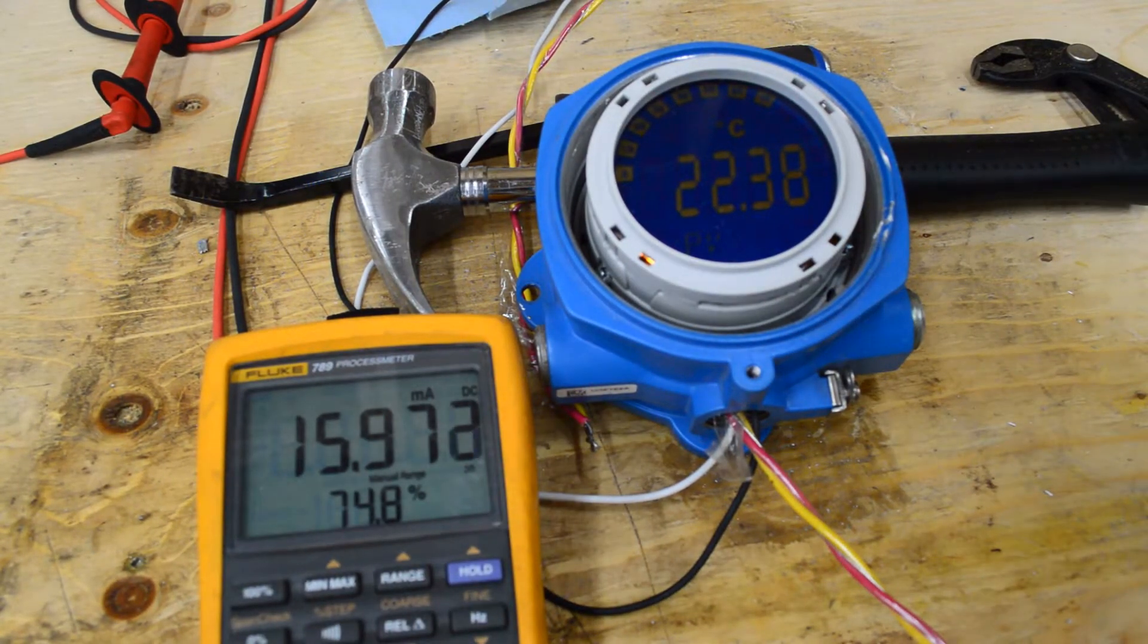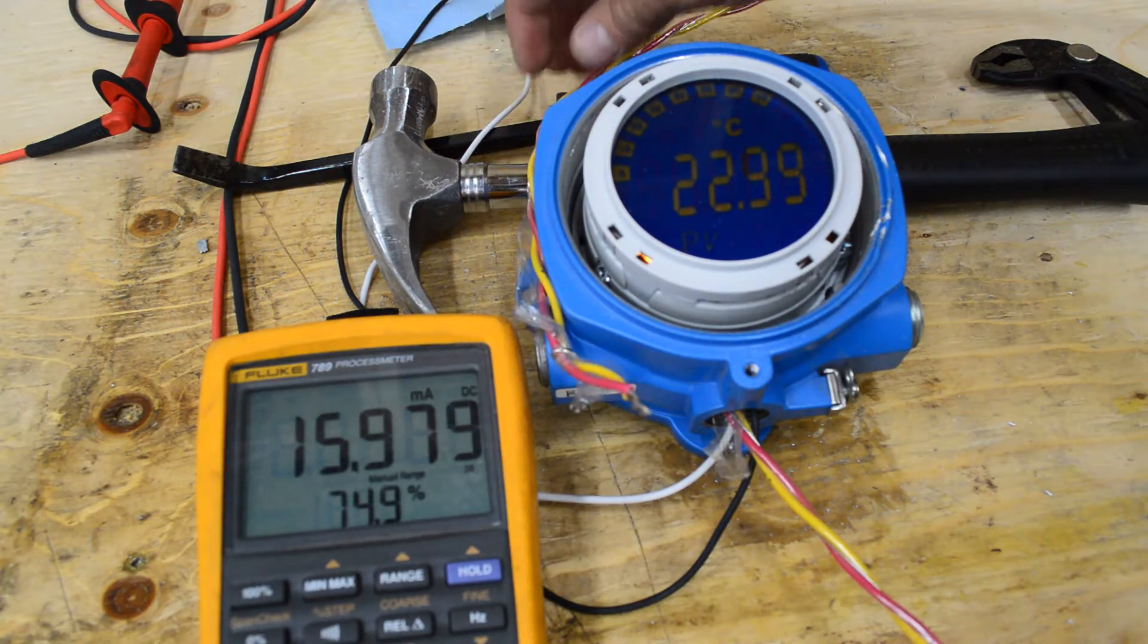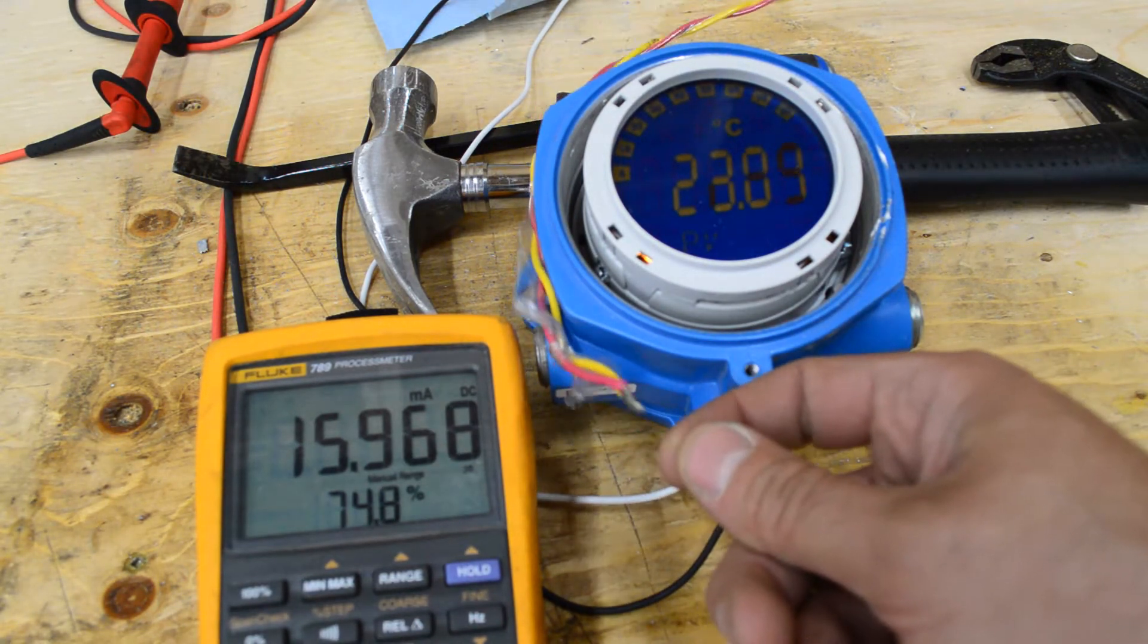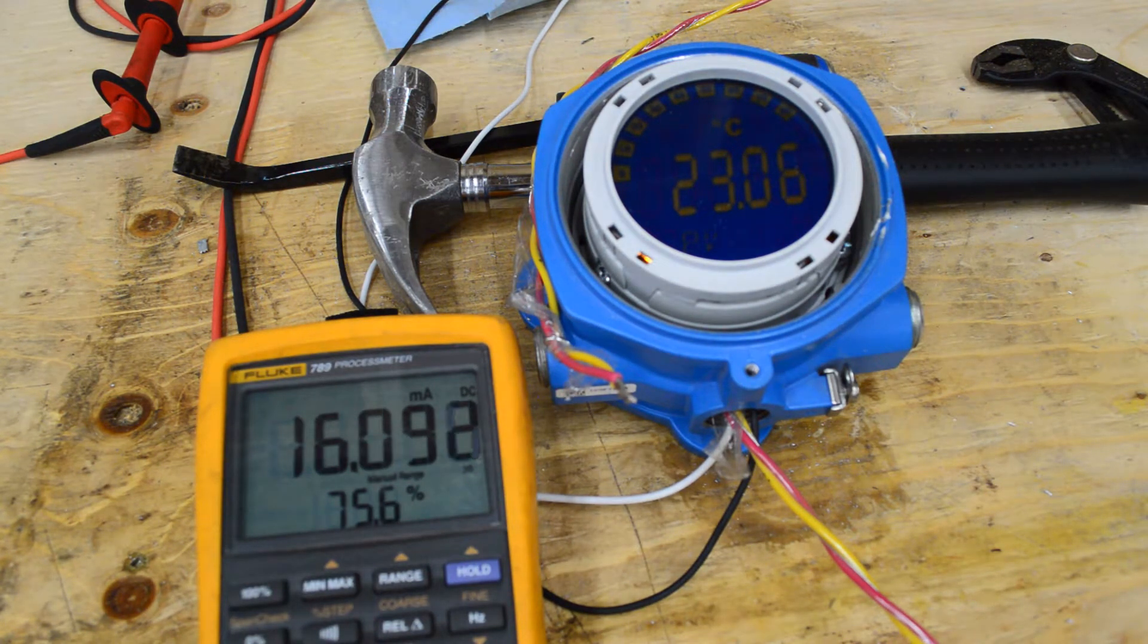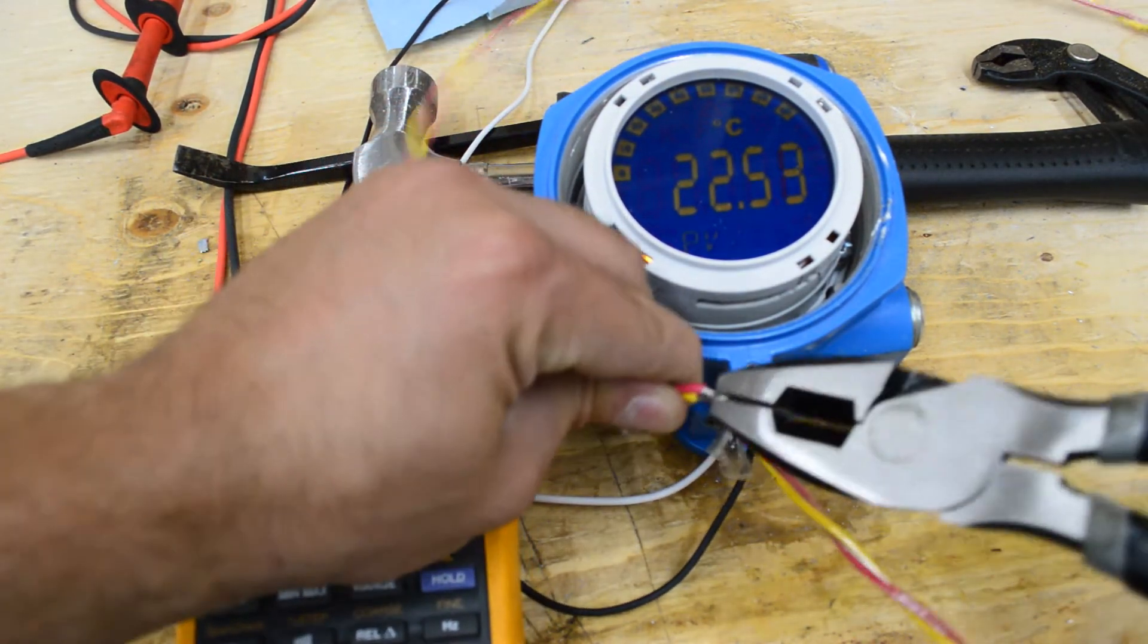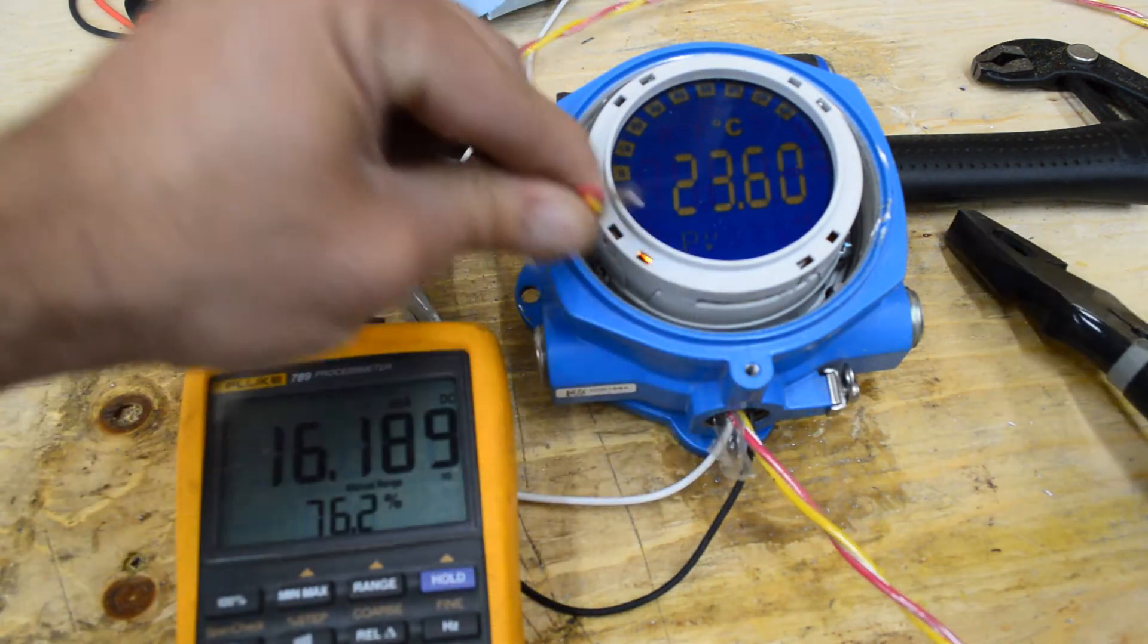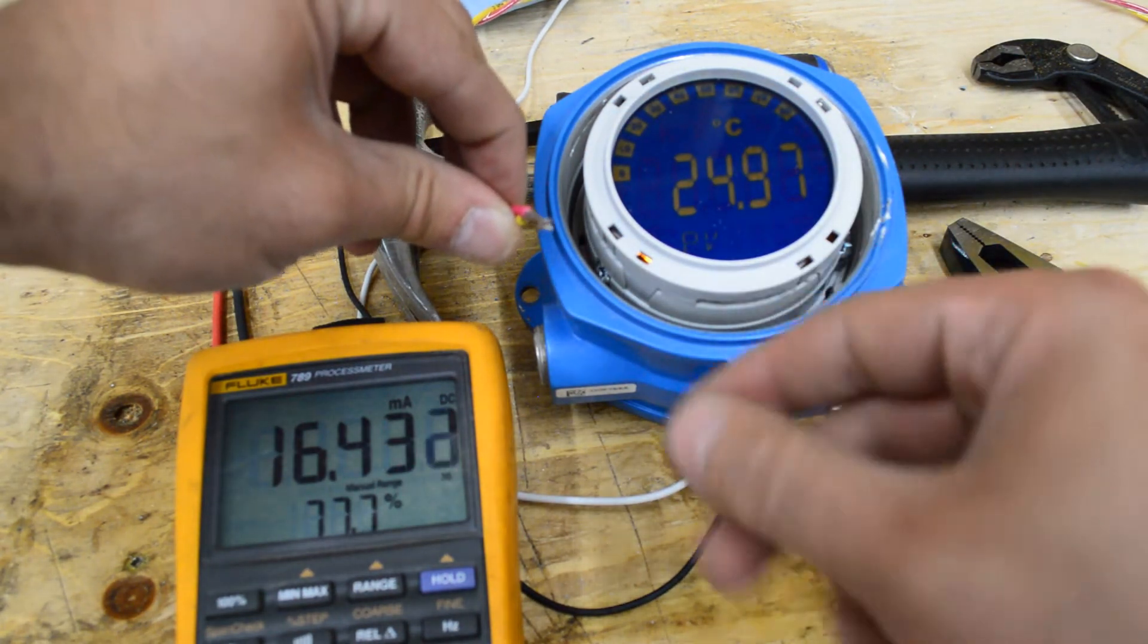There is one more thing that we should be checking here. That is the fail mode on it that I was talking about earlier. And that will come about if this junction here opens or if I cut the wire. So, if I untwist this, for now we have it set to go high. So we should get over 20 milliamps once I open this up.